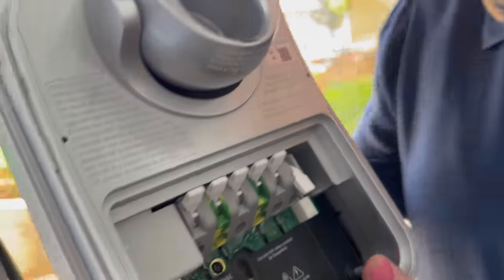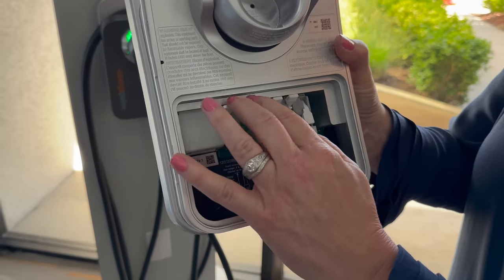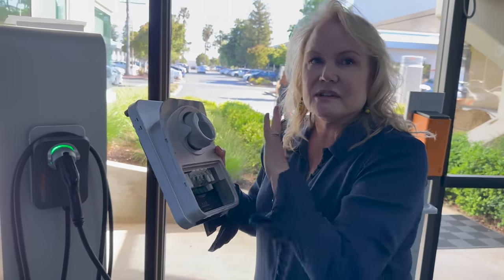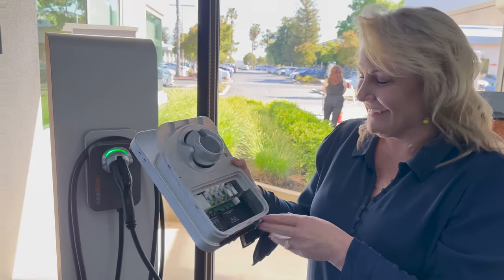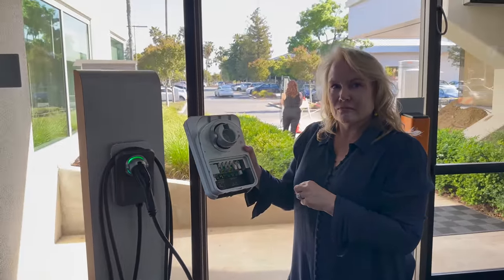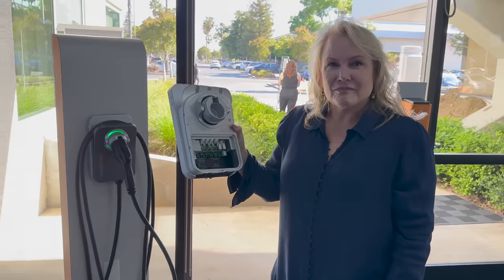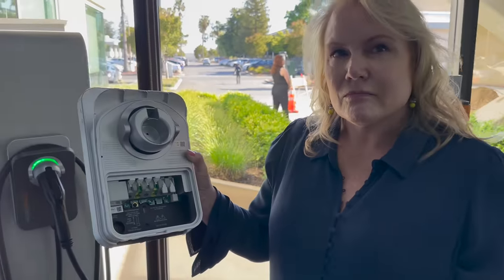With Wago connectors, you don't have to worry about torque or whether you got it tightened properly — you close it and it's done. This design is something not seen from other Level 2 units. From personal experience, a professional installer who didn't clamp down on lugs enough caused failures. With a solution like this, you clamp down and the pressure is there. If there's a problem with the NEMA connector because someone hasn't installed it correctly, the station still does its job.